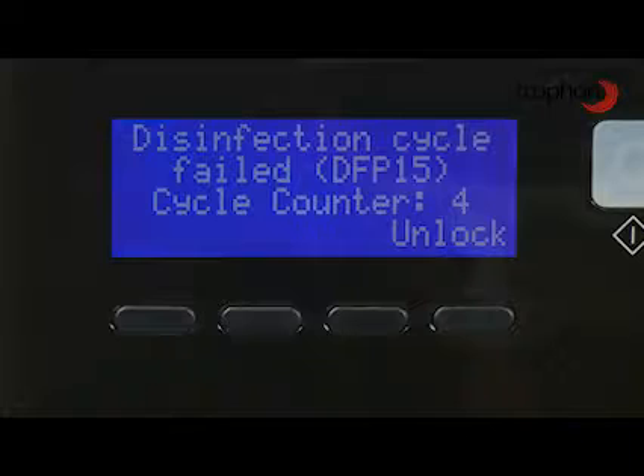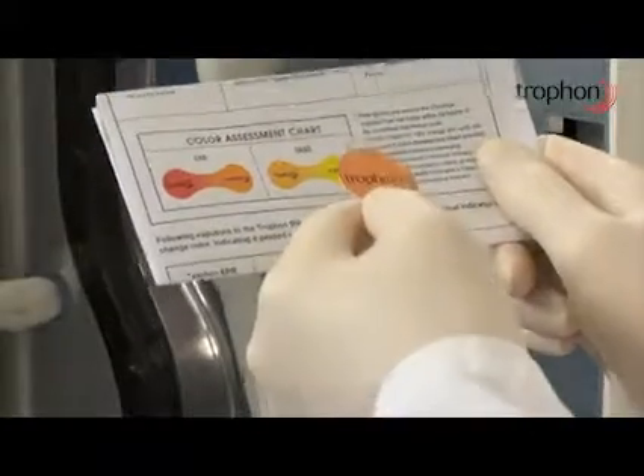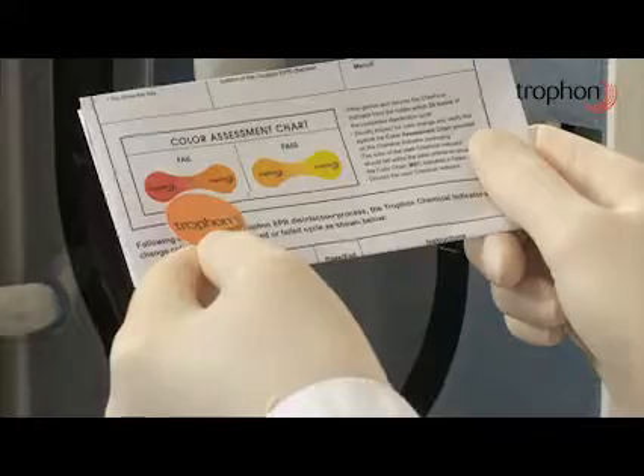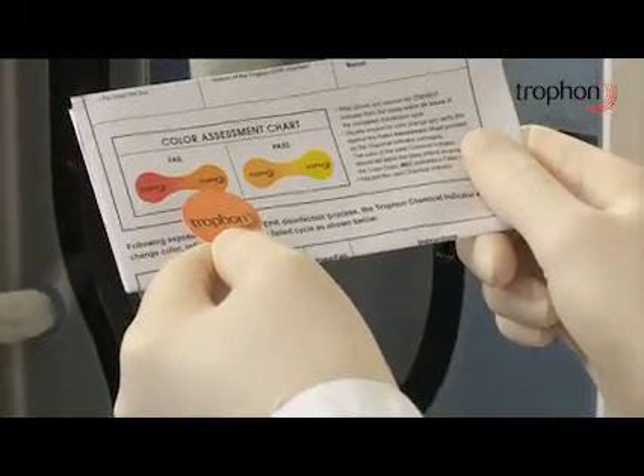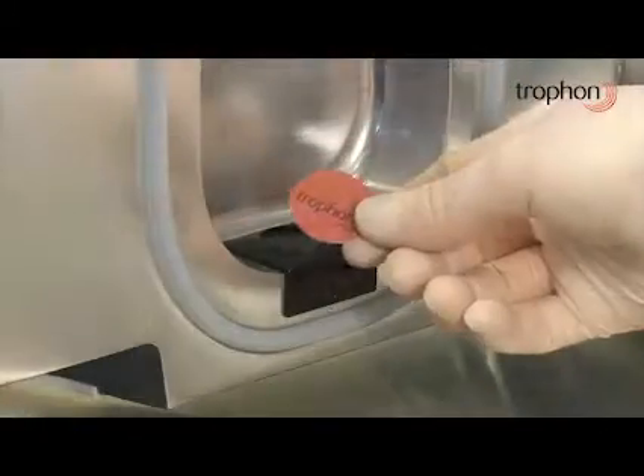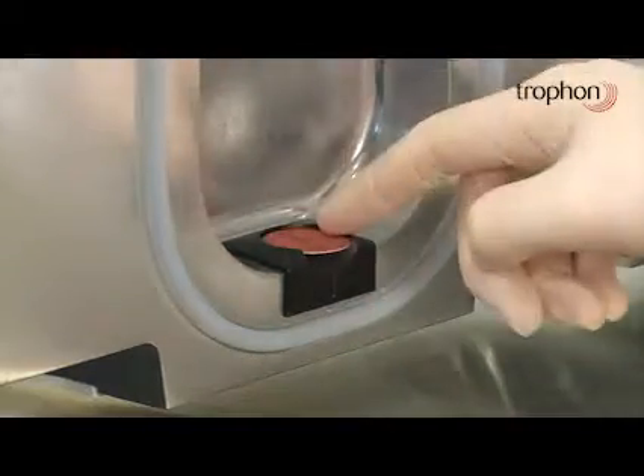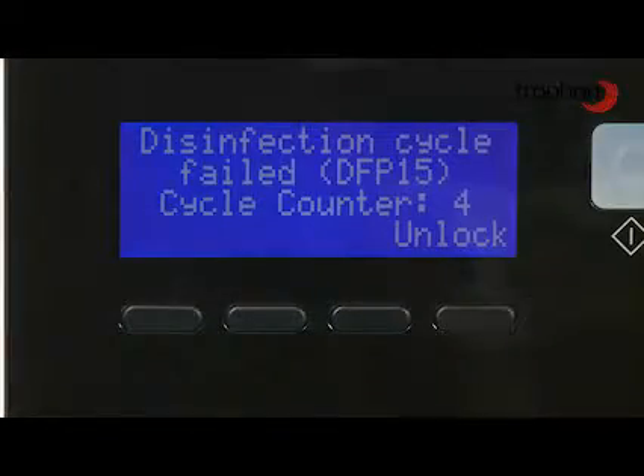In the unlikely event there is a failed disinfection cycle, this will be indicated by an on-screen message and/or an incorrect chemical indicator color. If this occurs, attempt a second disinfection cycle, ensuring a new chemical indicator is inserted. If the second cycle is unsuccessful, contact your local Trophon representative.